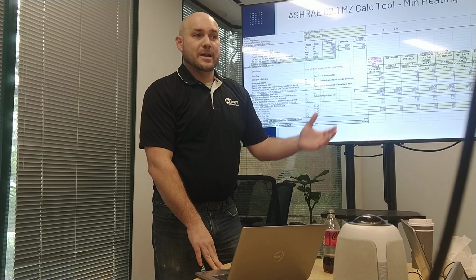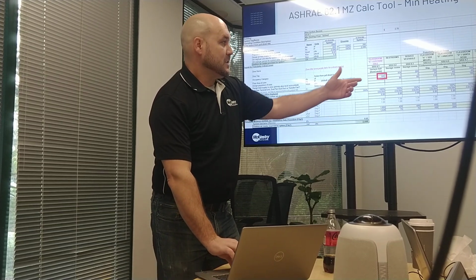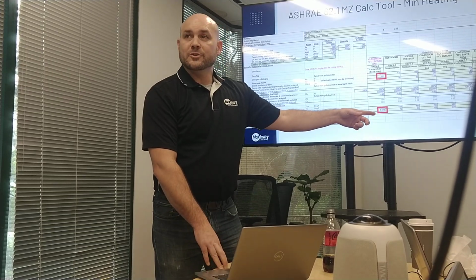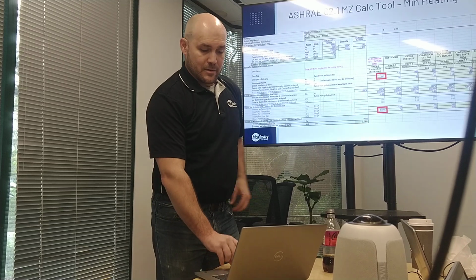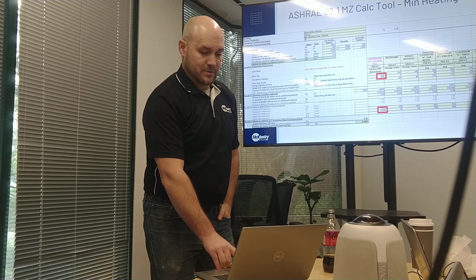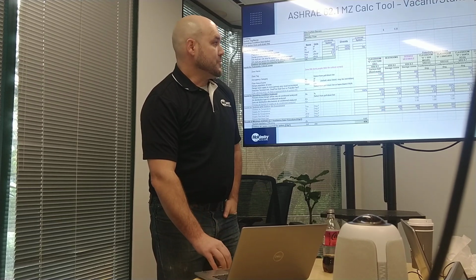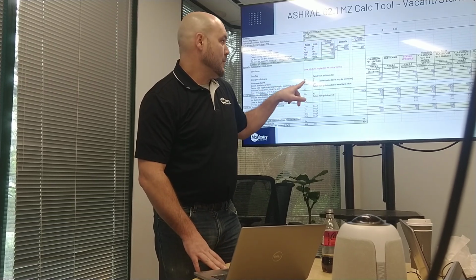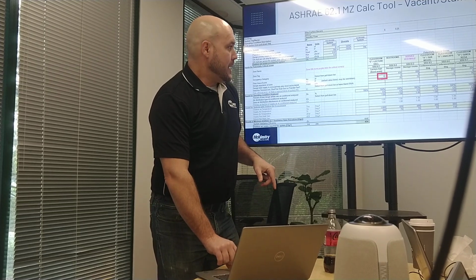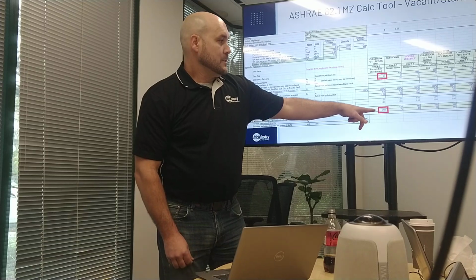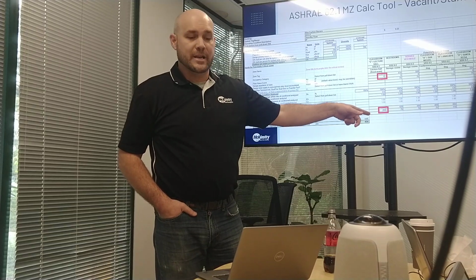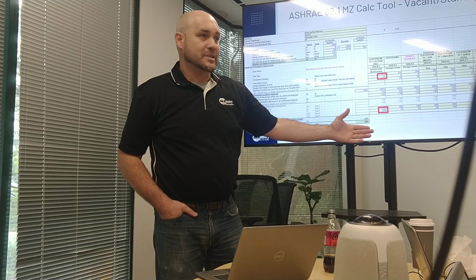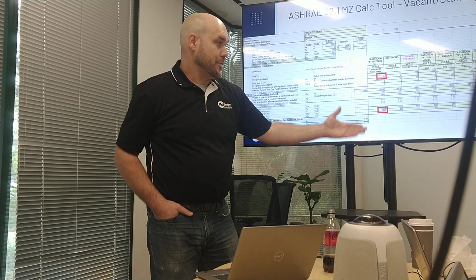So for the same space, but now you're supplying maybe 80, 85 degree air into the space. Still 100 people, but now you need over 1,000 CFM as your minimum ventilation requirement for that space, assuming that it's fully populated. Now, this is the vacant standby scenario, zone population goes to 0, and hey, what do you know? We only have to ventilate 200 CFM. That 200 is not a function of the ventilation, that's just as low as that box can go. That's a 14-inch box. It can only go down to 200 CFM. You only need to ventilate like 130 CFM into the space for that condition, but we can't control to 130, we can only control to 200.